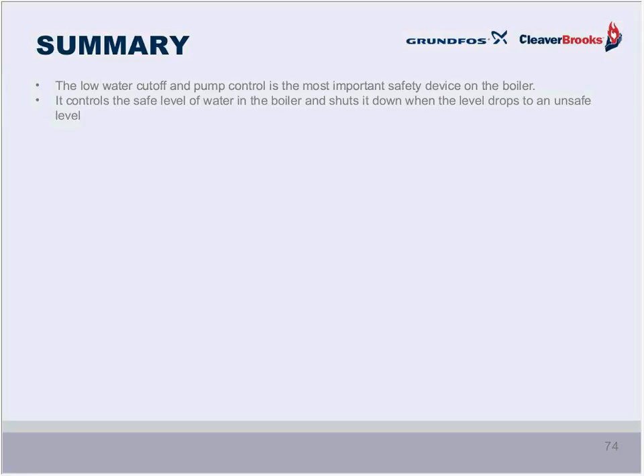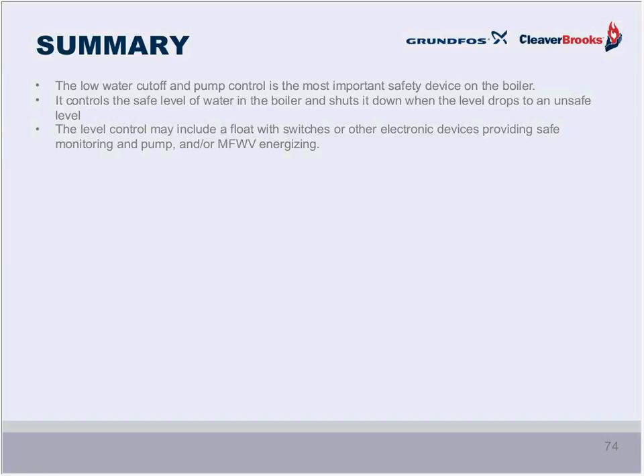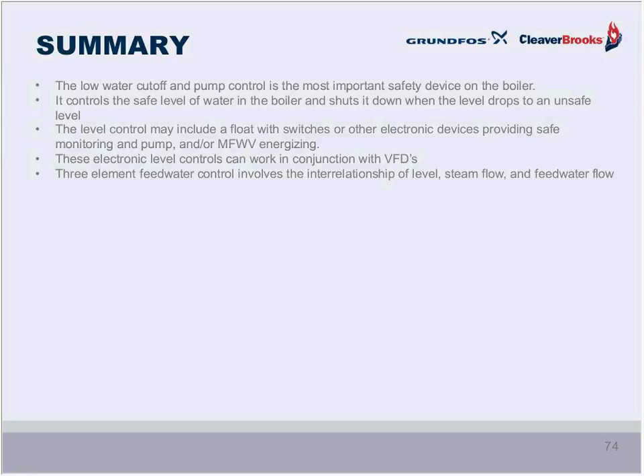I just want to go through a quick summary of what we covered today, at least our major takeaways. The low water cutoff and pump control is the most important safety device on the boiler, and I think I showed you why. It controls the safe level of water in the boiler and shuts it down when the level drops to an unsafe level. The level control may include a float with switches or other electronic devices, providing safe monitoring and pump and/or modulating feedwater control. These electronic level controls can work in conjunction with VFDs, as Jim was pointing out.